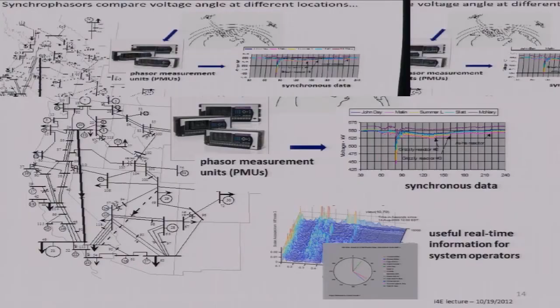Synchrophasor technology is a way to observe empirically at each node what those relative angles are. To do that you need enough resolution in the time dimension, because comparing the exact zero crossing of voltage at one node versus another involves a very small number of degrees - 360 degrees corresponds to 1/60th of a second. You need to compare your time at different locations so you can make essentially simultaneous measurements, so each measurement has to be time-stamped.